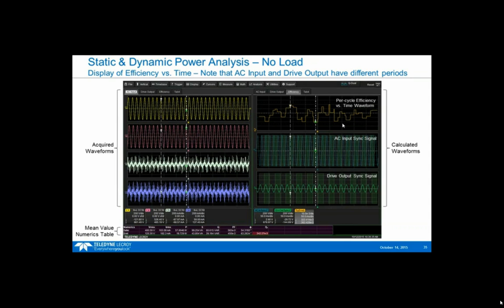Now what's interesting here is the AC input signal is 60 hertz. The drive output signal in this case is 45 hertz. So they don't match up. They're not coincident. So when you see this signal have quite different periods of time for when the level is at a certain level, it's only because there's a new efficiency calculation every time there is a transition in one of these two waveforms. So in total there are n different periods here and maybe m different periods here, so you have n plus m different periods.